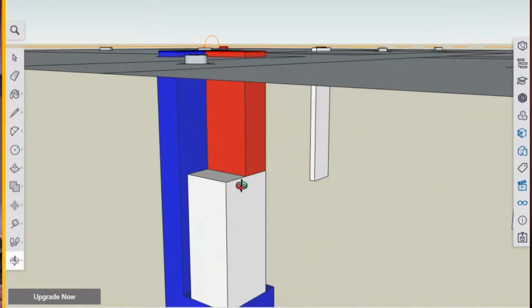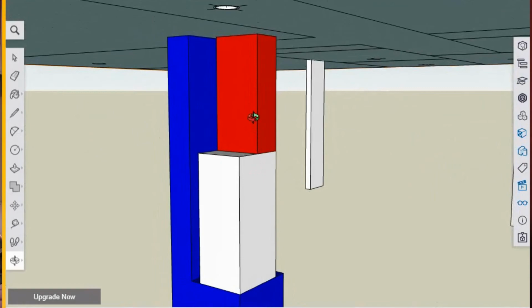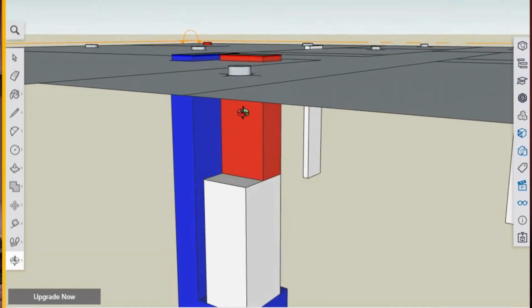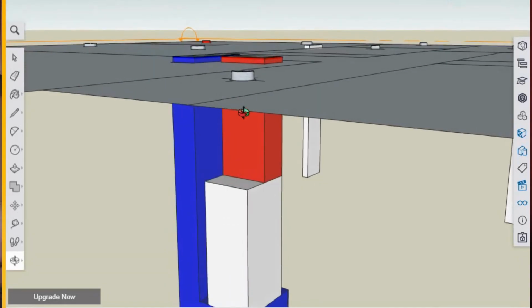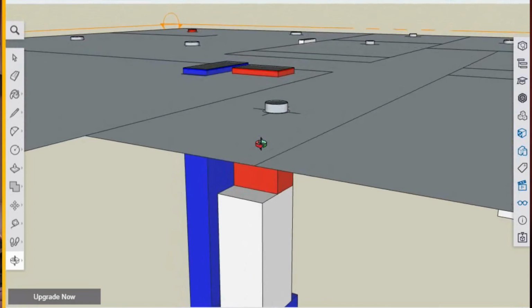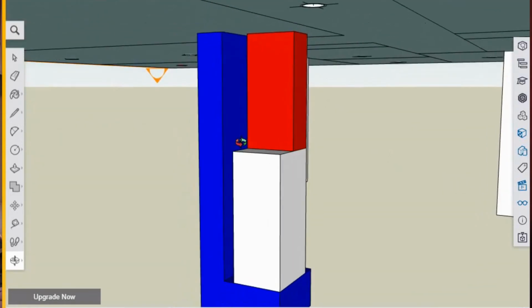The only thing to consider here, whenever you're doing this, is that you will very likely have to put your fire dampers in so that the likelihood of flame spread is decreased. But yeah, if you just put a fire damper in the supply and return, you'll be safe there.